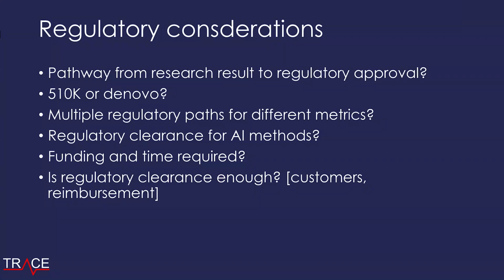I was going to say, there's pre-market approval and then post-market authorization, right? There's pre-market and post-market activities. The pre-market approval allows you to market your medical device, and it's required regardless, as long as you're classified as a medical device. It's just the pathway that is different. The PMA is more of an approval process, and the 510K is called a clearance, but those are still pre-market approvals. Once your device gets pre-market approved, then you can start marketing it, but you can't distribute it until you do a registration with the FDA. And those are the split between the pre-market and post-market activities.